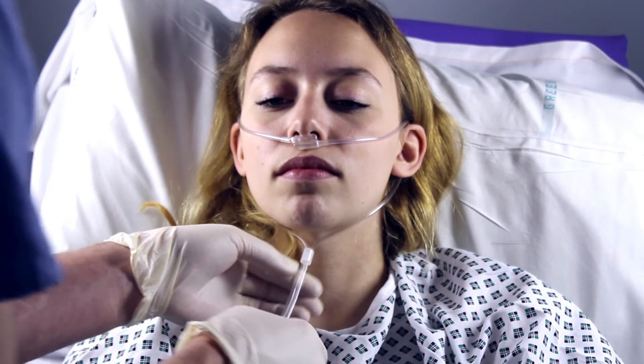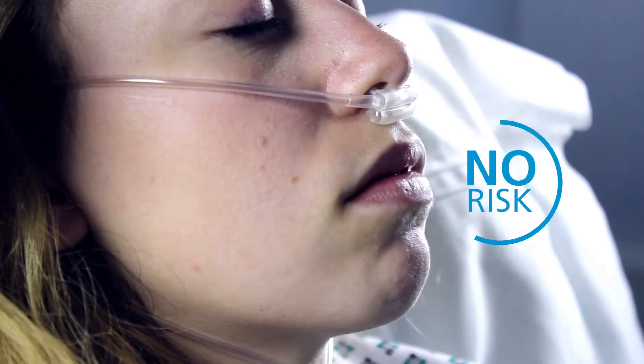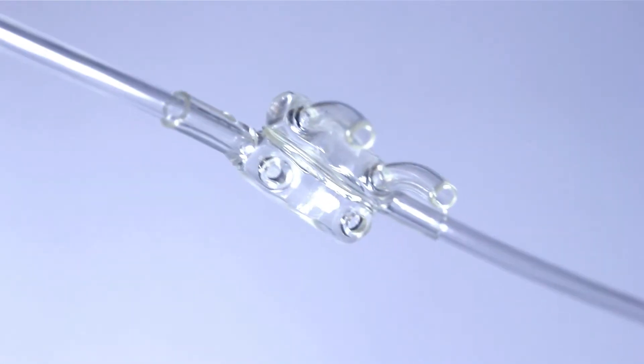The CO2 sampling is taken from both nostrils and there is no risk of mixing with fresh oxygen, as the patient's expiratory flow will divert fresh gas away from the sampling prongs. CO2 is sampled from both nostrils for side stream CO2 monitoring through the upper prongs. Fresh oxygen is delivered to both nostrils via the lower prongs of the Joule nasal cannula.